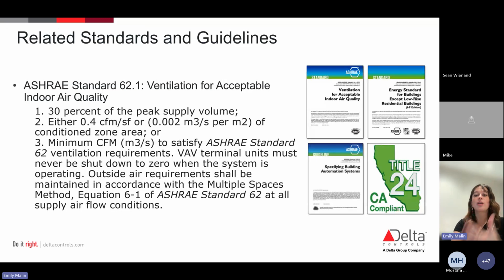So again, that's by no means everything that you might be monitoring, but it takes us to a good point where we can start to think about how all of these are working together in order to be controlled and what inputs and outputs we're going to have. I mentioned that we would look at this slide one more time, and this is what we saw in 101 around our industry standards. Our industry standards are ever changing and ever adopting. Right now we have 62.1, and that's going to be that ventilation for acceptable indoor air quality. That's the one that I was saying, even though we might not need to change the set point in that space, say we're all very comfortable in that space, there is a set amount that needs to always be filtering through in order for acceptable indoor air quality.